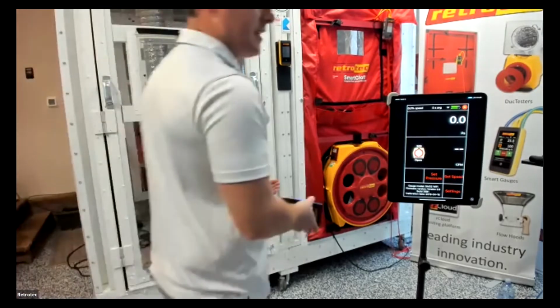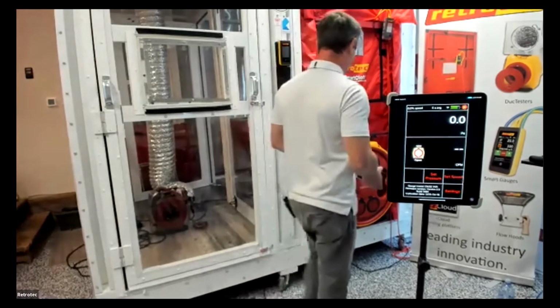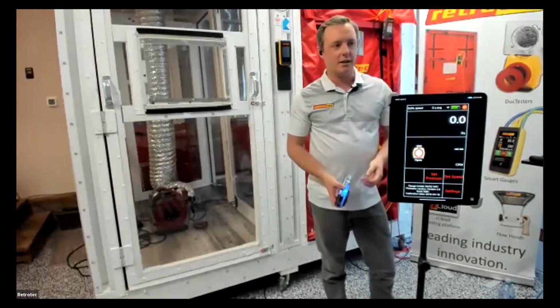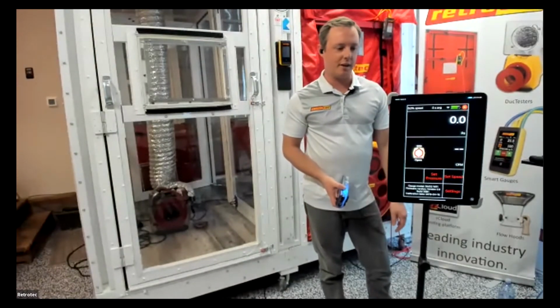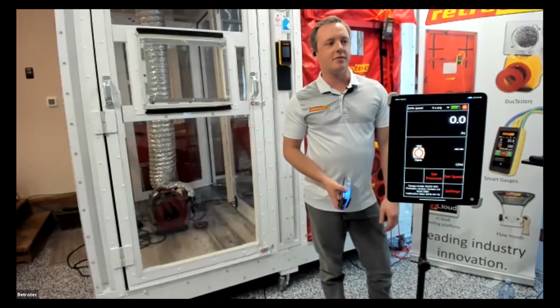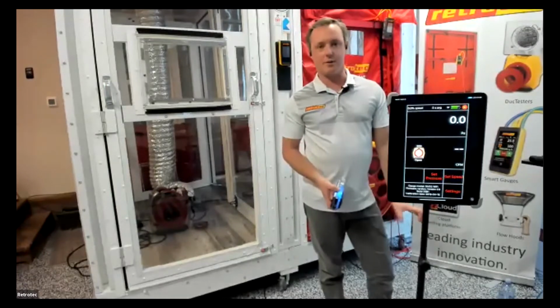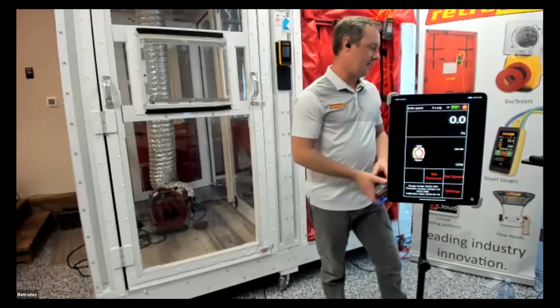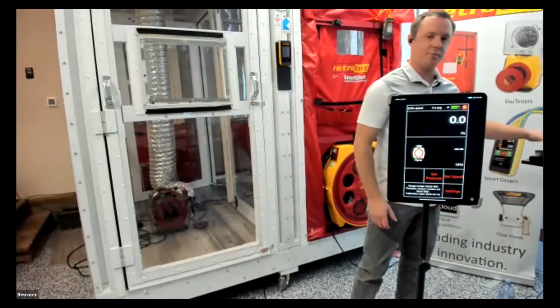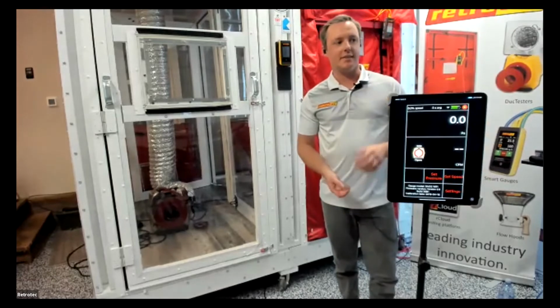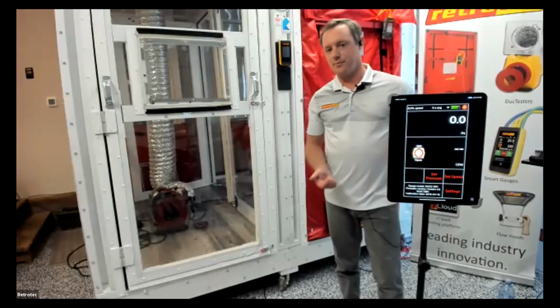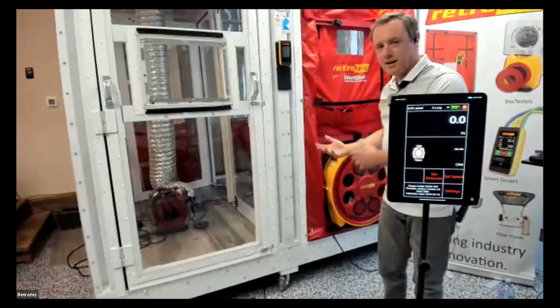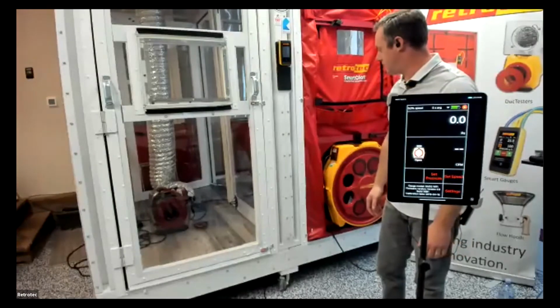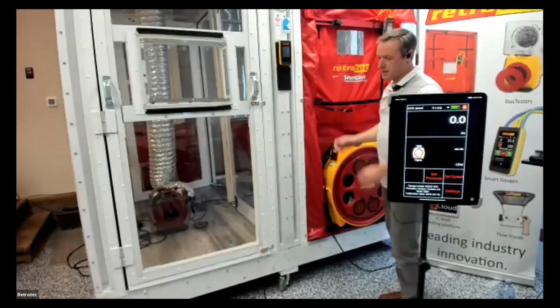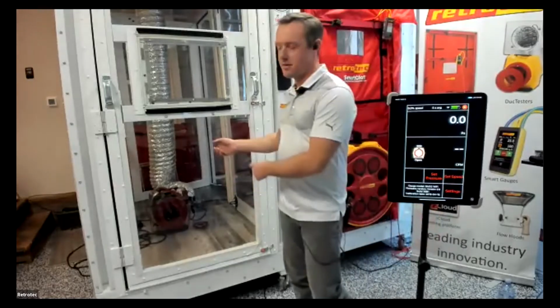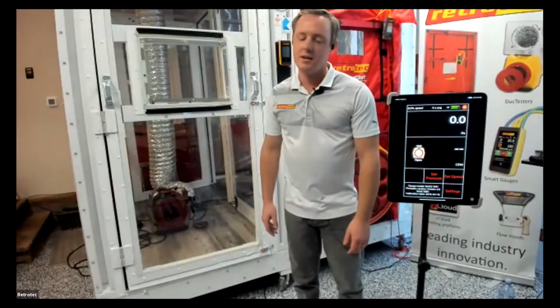So when we do this kind of test, we'll set up the blower door just like we do if we were just going to do a regular blower door test. The only difference is instead of seeking 50 pascals of pressure, we're going to have it seek 25. And the important thing to remember is we want the blower door and the duct tester facing in the same direction. So if we're pressurizing with the blower door, then I want to be pressurizing with the duct tester as well.